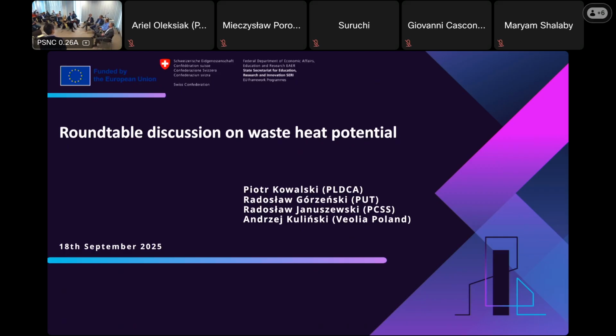But if we're looking at scale, we will have to include an additional component that raises the grade of heat from the level we're able to provide to the level the district heating network operates at. That's a CapEx issue—less of a technical issue, but a CapEx one. And an even bigger challenge is that it requires a lot of footprint. So to make it happen, one has to plan in advance. It's not something where we can independently build a data center and then somehow connect it to a district heating network—this kind of solution must be planned in advance. That's one of the biggest obstacles, because it requires upfront planning, and that's something we're often not very good at.